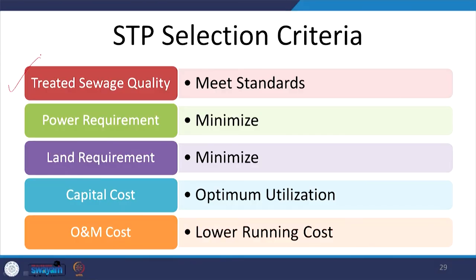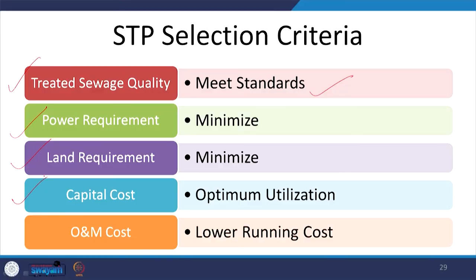When selecting an STP for any given project we have to consider several parameters: the quality of treated water coming out must meet CPCB standards; we must minimize power requirements; we must minimize land requirement if not enough land is available — though if land is abundant, stabilization ponds and root zone treatment can also be used. We have to optimize capital cost, avoid over-treatment beyond what is required, and reduce operations and maintenance cost. Based on these parameters we select the right type of STP and design it appropriately.